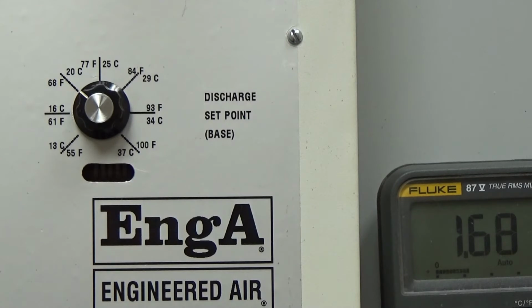Once your multimeter leads are installed on the test pins, a voltage will appear on your multimeter. 1 volt DC is equal to 10 degrees Celsius. In this case, the meter is reading 16.8 degrees Celsius. The set point dial on the GTRAC2 is set for 20 degrees Celsius. The set point will have to be calibrated.